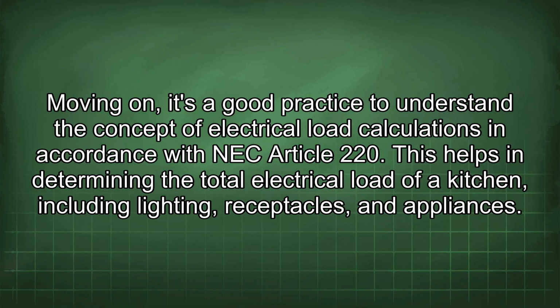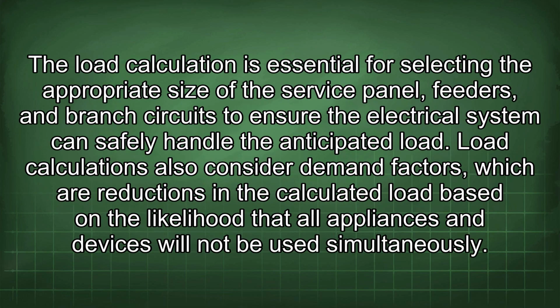Moving on, it's a good practice to understand the concept of electrical load calculations in accordance with NEC Article 220. This helps in determining the total electrical load of a kitchen, including lighting, receptacles, and appliances. The load calculation is essential for selecting the appropriate size of the service panel, feeders, and branch circuits to ensure the electrical system can safely handle the anticipated load. Load calculations also consider demand factors, which are reductions in a calculated load based on the likelihood that all appliances and devices will not be used simultaneously.